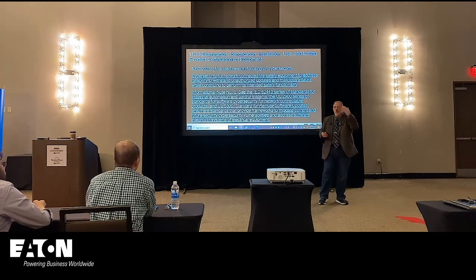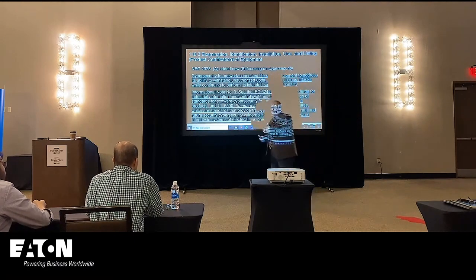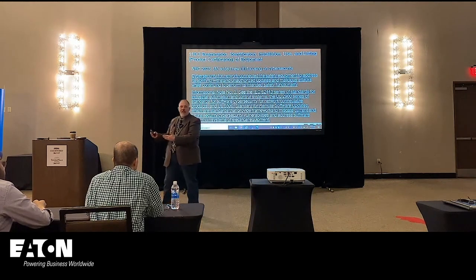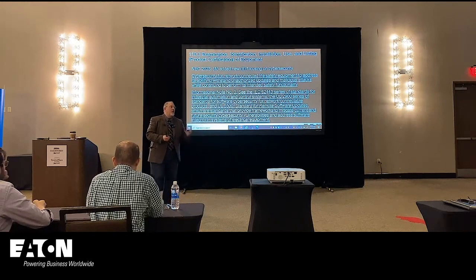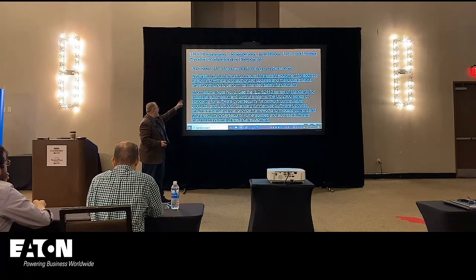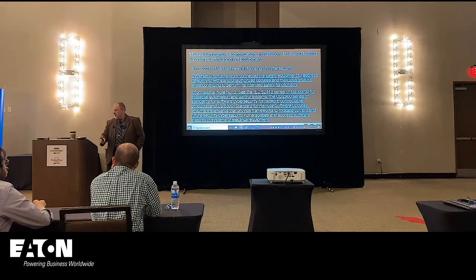That's the document that's enforced and adopted by states. And so if you don't have it in the NEC, it becomes like a 70E document, which is only enforced after the fact if you have a problem. So in any case, we have a requirement in list item 8 that says cybersecurity for network-connected life safety equipment to address its ability to withstand unauthorized updates and malicious attacks while continuing to perform its intended safety functionality.